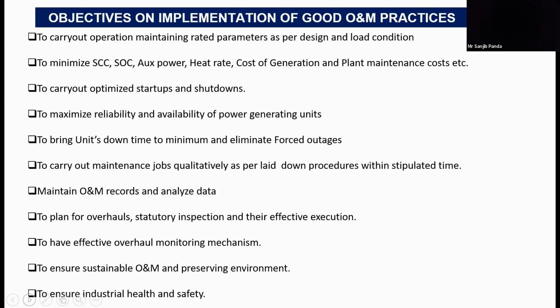Second is to minimize the parameters and the TPs, specific, whether it is specific coal consumption, specific oil consumption, auxiliary power, heat rate, cost of generation and plant maintenance cost, etc. Third is to carry out optimized startups and shutdowns. So when we are following the good O&M practices, obviously the focus will be on to keep the equipment and maintenance always prepared, so that whenever we carry out startups and shutdowns, we are able to do it in the optimum given time and not make delays.